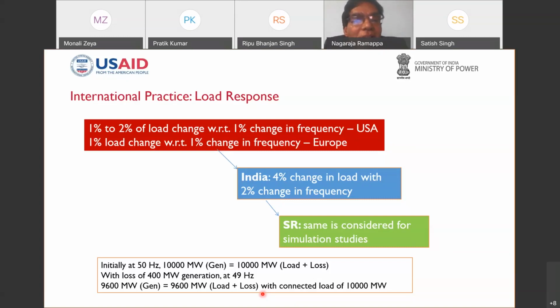Therefore, in the USA, they talk about 1 to 2% of load change with respect to 1% change in frequency, and 1% load change with respect to 1% change in frequency in Europe. But this characteristic depends upon the composition of the load and what demand you are serving, whether it is agriculture pump set load or air conditioning load. It all depends upon that. In India, a 4% change in load with a 2% change in frequency is what is considered. What it means, let us try to understand.